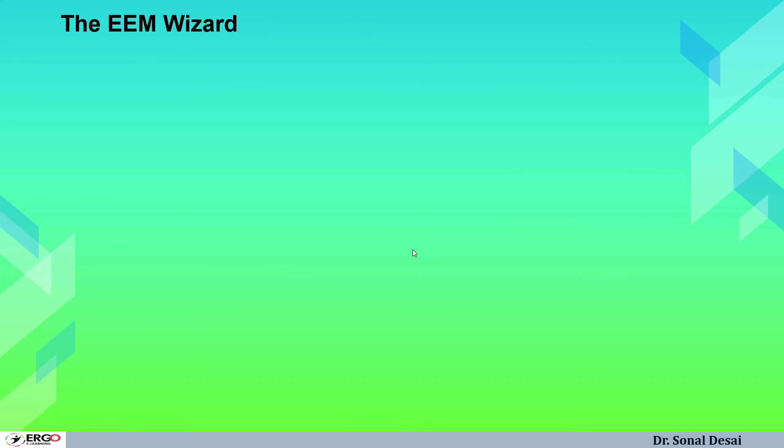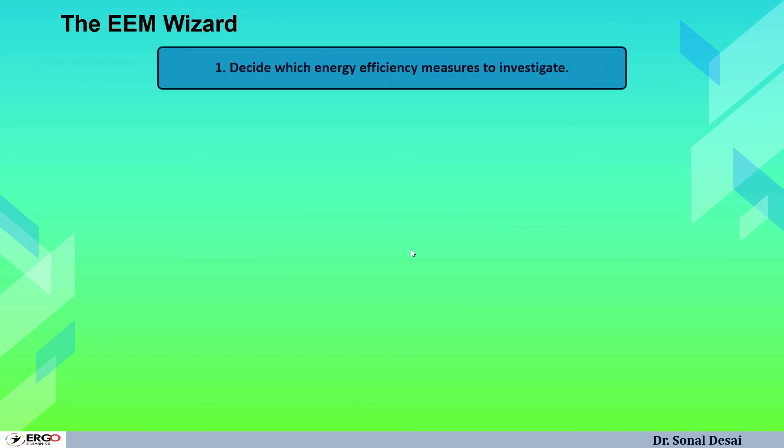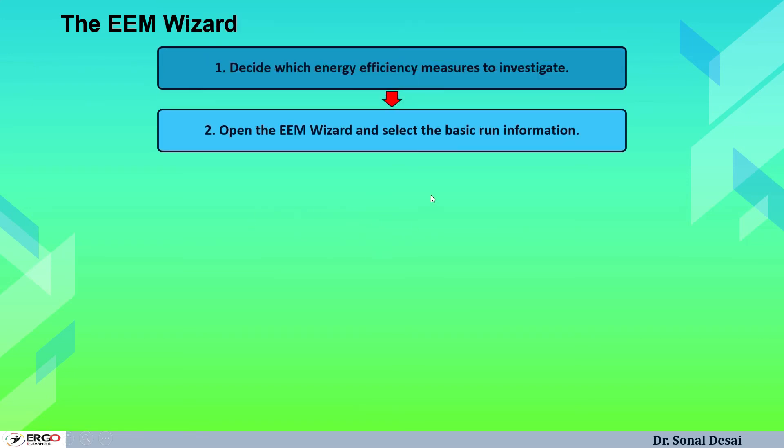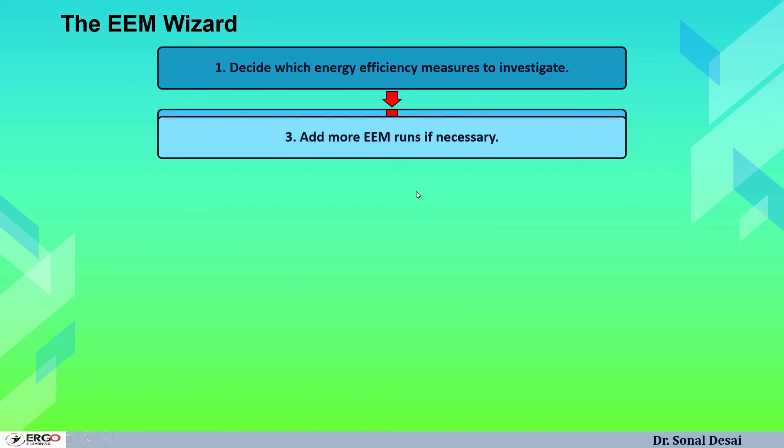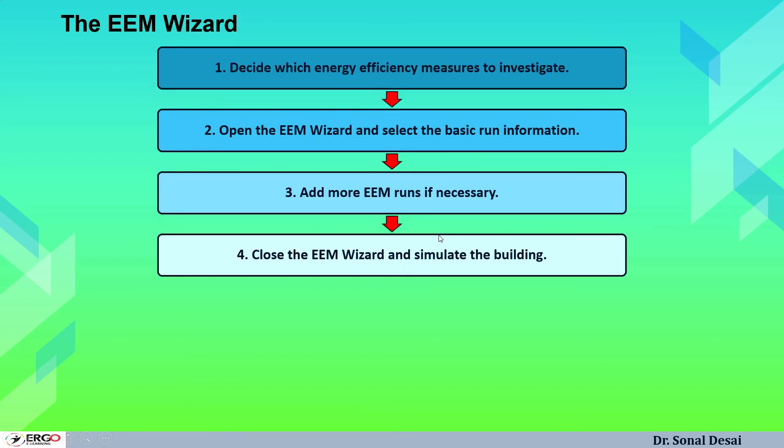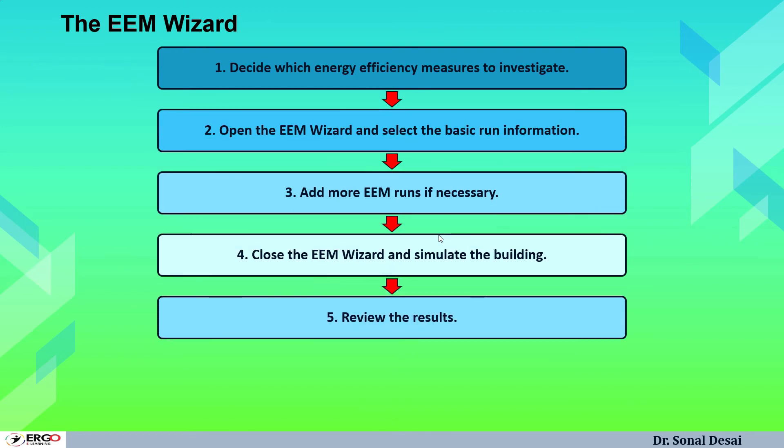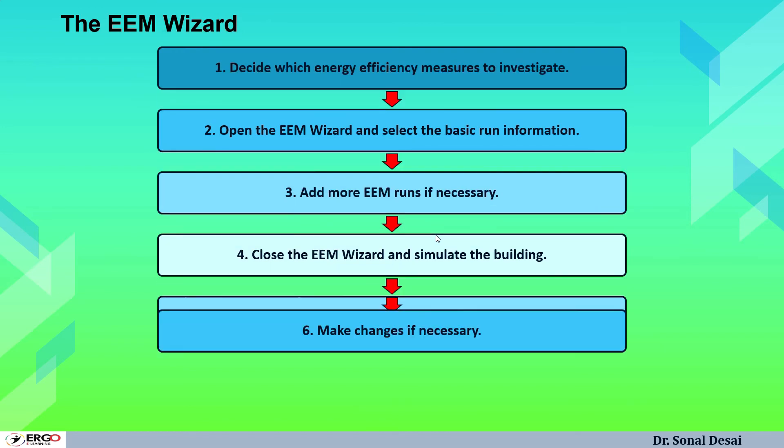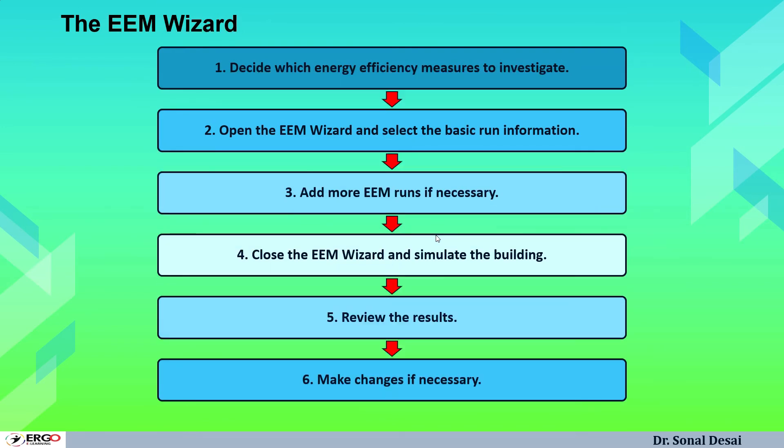The most important part of eQuest software is EEM wizard, that is energy efficiency measure. After drawing a building model, we can apply certain energy efficiency measures so that we can evaluate how building is going to perform when we apply certain energy conservation methods. They decide which energy efficient method is most appropriate. Once we are targeting EEM, we have to decide which EEM we are talking of, then go for EEM wizard and select the basic run. We have to apply EEM or we may add couple of EEMs together and compare them, then simulate the building followed by generation of results. If required, we may change those EEMs and redo the entire procedure.